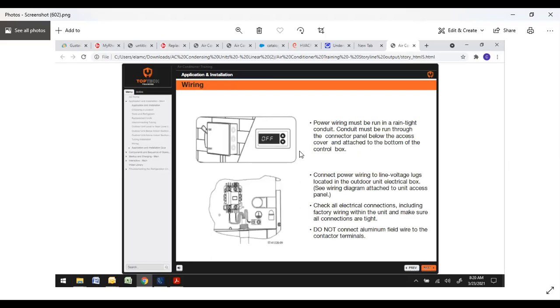It is important that your power wiring must be run in a rain-tight conduit. Conduit must be run through the connector panel below the access cover attached at the bottom of the control panel. Connect power wiring to the line voltage lug located at the contactor right here. Make sure all your electrical connections, including factory wire connections, are tight. Just because they're factory, don't necessarily assume that they're correct. While you're in there tightening these up, go ahead and make sure everything else is tight too.